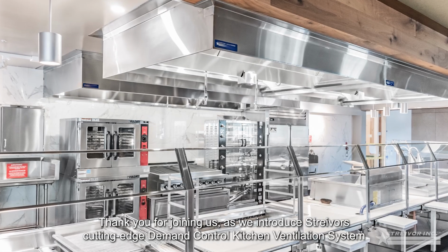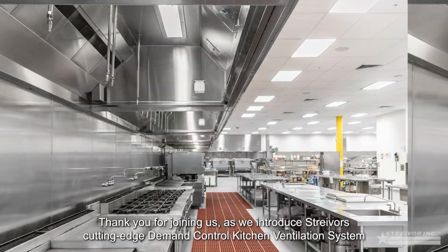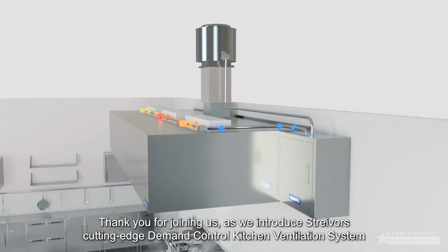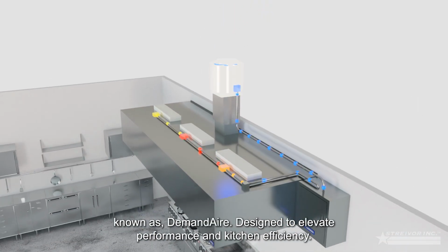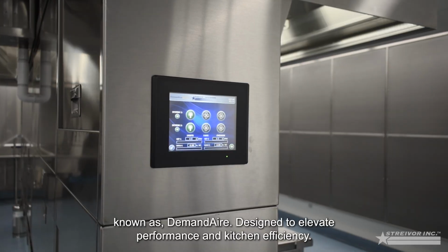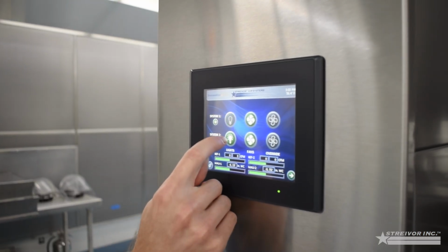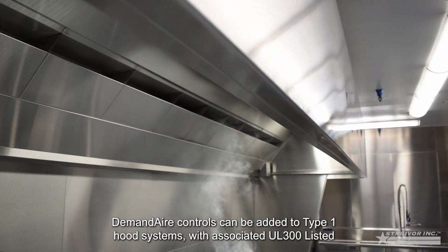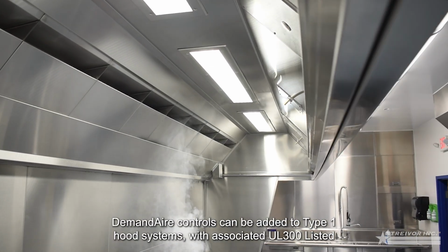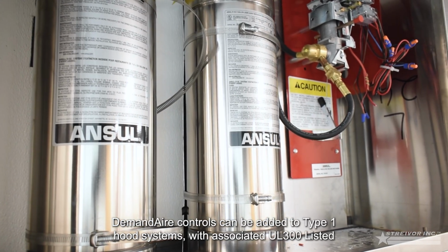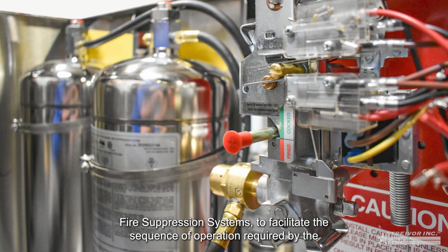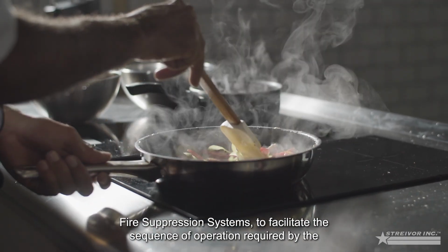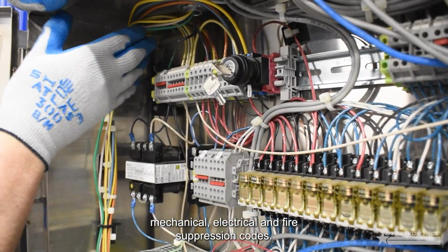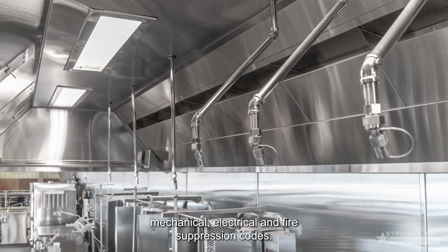Thank you for joining us as we introduce Streivor's cutting-edge demand control kitchen ventilation system, known as DemandAire. Designed to elevate performance and kitchen efficiency. DemandAire controls can be added to Type 1 hood systems, with associated UL 300 listed fire suppression systems, to facilitate the sequence of operation required by the mechanical, electrical, and fire suppression codes.